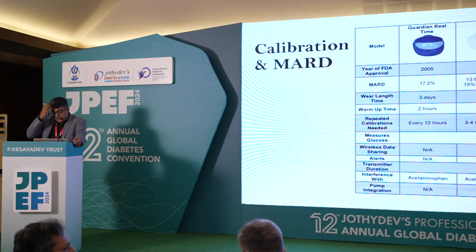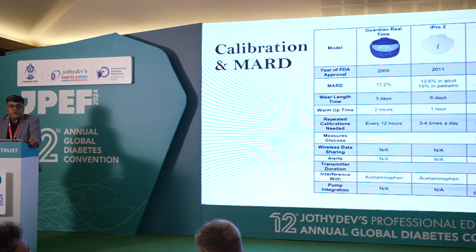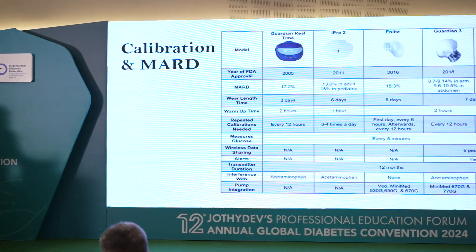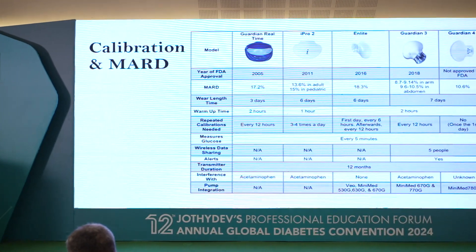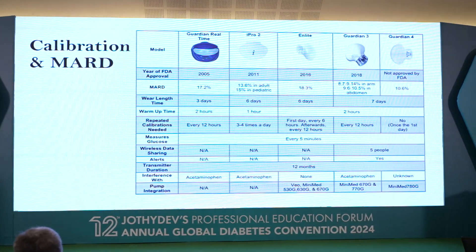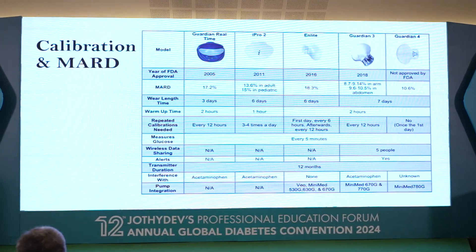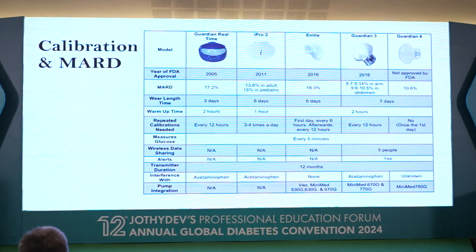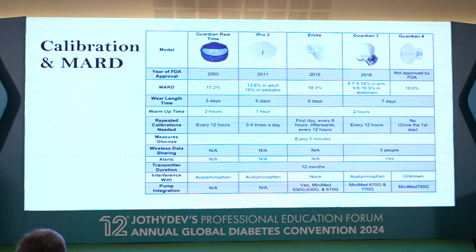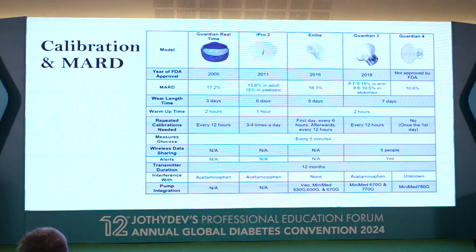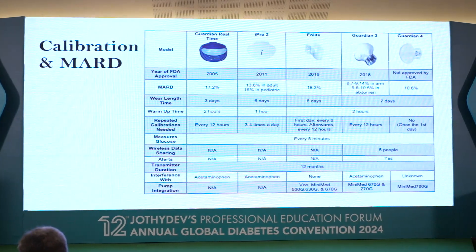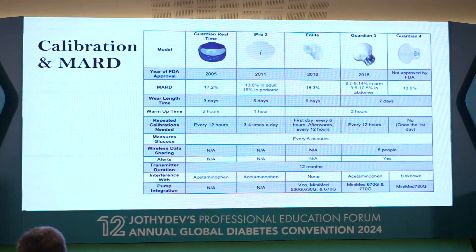Some CGM devices need to be calibrated while others do not. MARD is the parameter used to test the accuracy of a CGM device. Earlier devices had a MARD of 12–14%; recent devices are coming with a MARD of less than 10%, which is the ideal. The devices we currently have available do not have MARD less than 10%, but the latest devices do. For Medtronic devices, the MARD of the Guardian 3 is around 9%, which is acceptable. The sensor life is 7 days and there is a warm-up time of 2 hours. Substances like acetaminophen can interfere with readings on the Medtronic device.